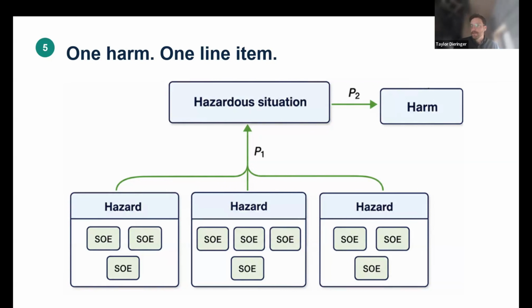And then just to really hammer home the control in P2: what does a control in P2 look like? Oftentimes these are some type of protective measure put in place to alert the user that the medical device has entered a condition that could lead to harm. So for this example, where we're talking about a patient experiencing a burn, maybe the device has a thermocouple or some type of temperature monitoring sensor. And as it increases in temperature, we get an LED that blinks. So that LED is technically a control we have in place in the form of a protective measure to alert the user that there's a hazardous situation.